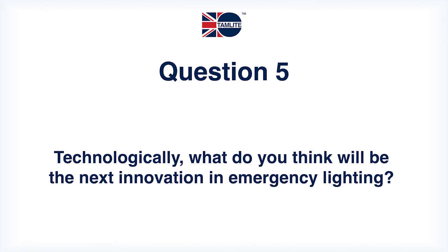And the services engineer in the central location can test all the emergency lighting across his estate in the city overnight on a weekend without him being on site. He turns up in the morning, looks at the test report, and it's all been done wirelessly, remotely, sent back to a central data point, and he can review it from there. So that kind of technology is really available now, and people are beginning to see the benefits and taking advantage of it. Yeah, excellent.